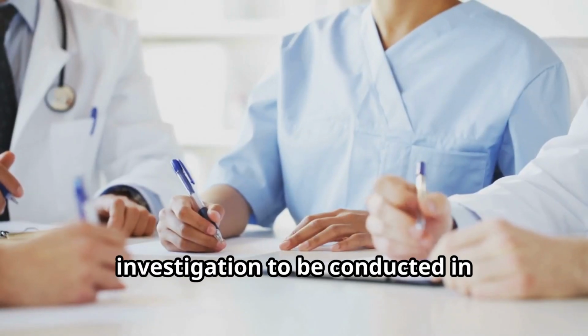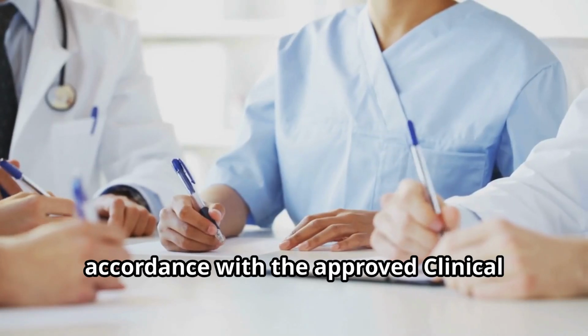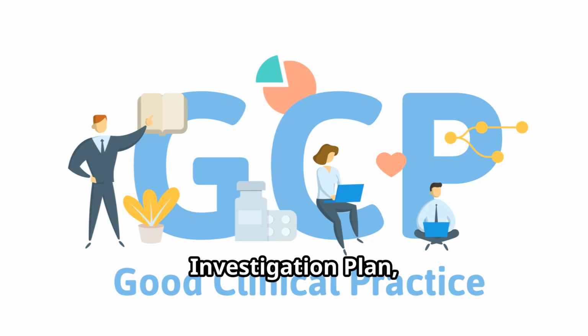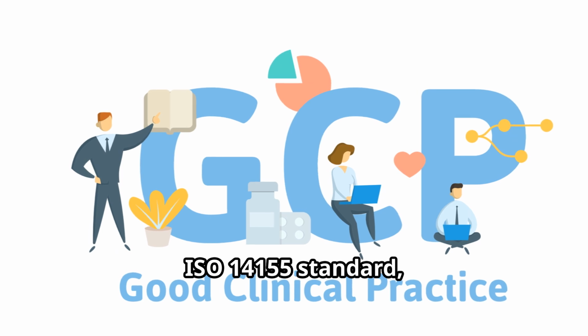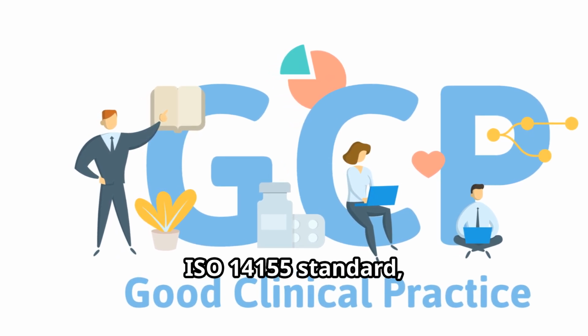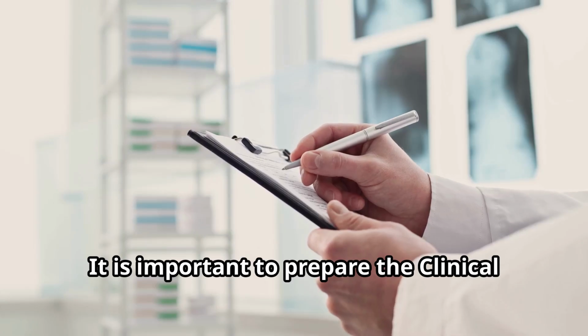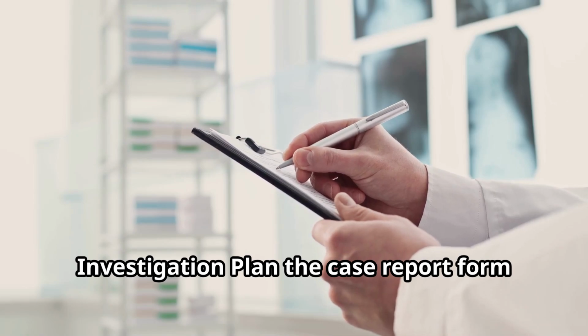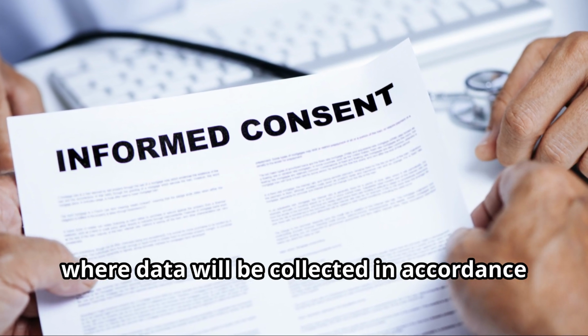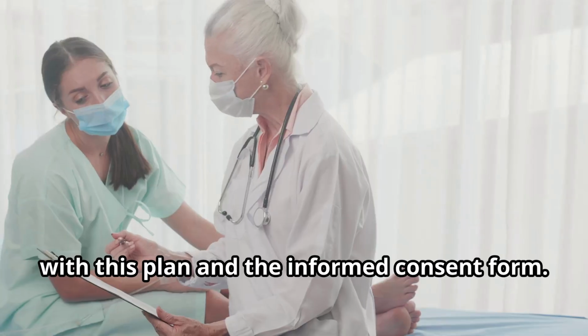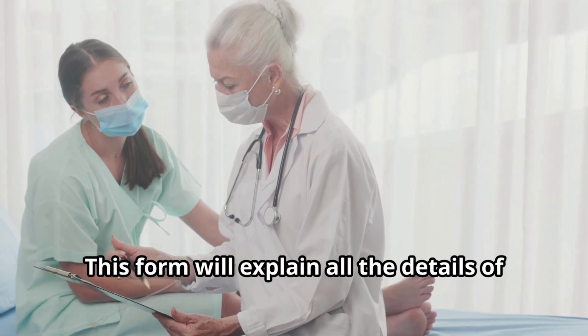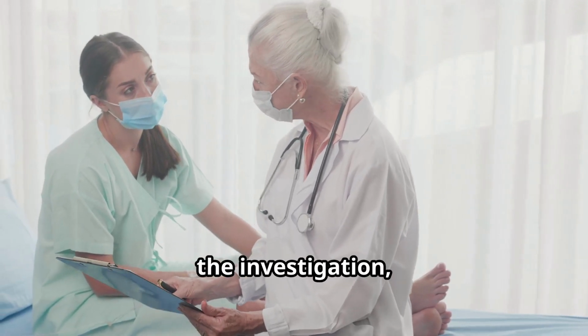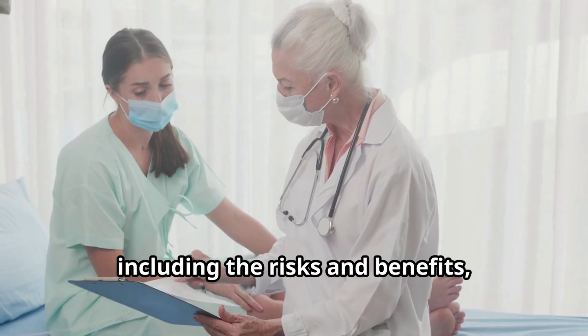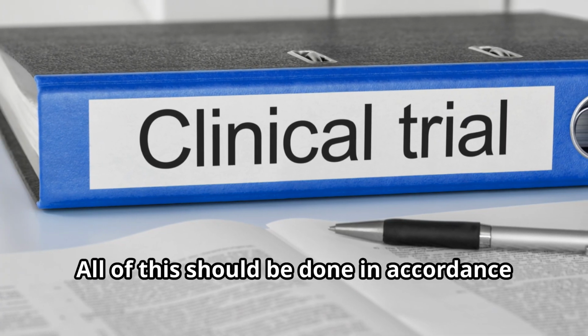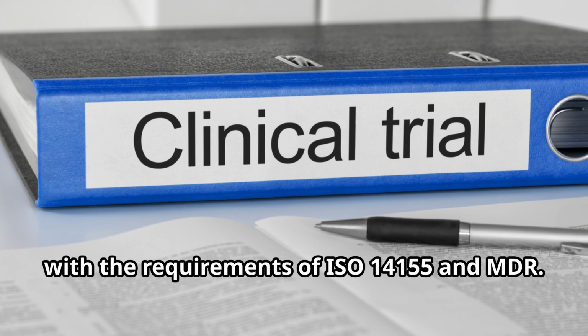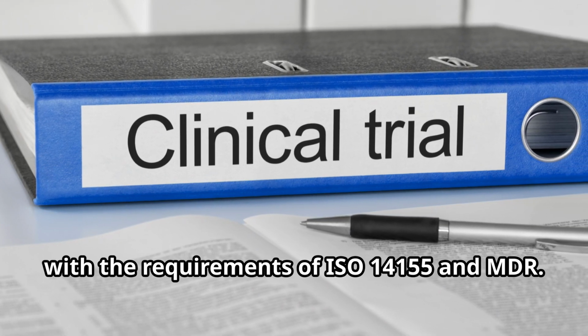Authorities expect the clinical investigation to be conducted in accordance with the approved clinical investigation plan, Good Clinical Practices, ISO 14155 standard, and MDR. It is important to prepare the clinical investigation plan, the case report form, where data will be collected in accordance with this plan, and the informed consent form. This form will explain all the details of the investigation, including the risks and benefits to the subjects. All of this should be done in accordance with the requirements of ISO 14155 and MDR.